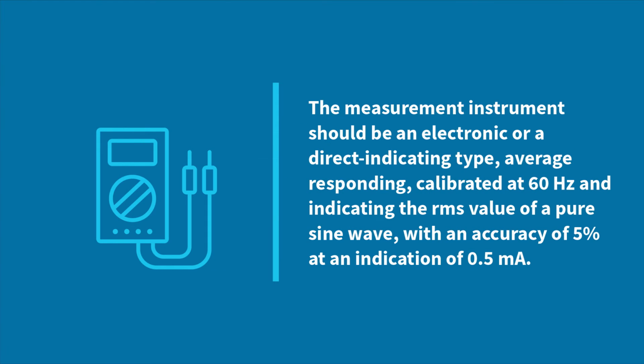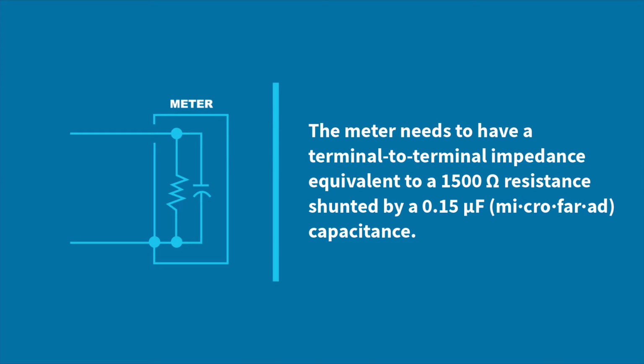The measurement type instrument should be an electronic or direct indicating type, average responding, calibrated at 60 Hz, and indicating the RMS value of a pure sine wave with the accuracy of 5% at an indication of 0.5 milliamps. The meter needs to have a terminal-to-terminal impedance equivalent to 1,500 ohms resistance shunted by a 0.15 microfarad capacitance.